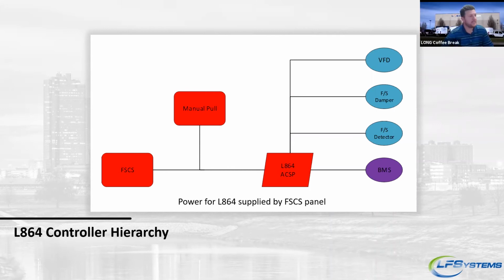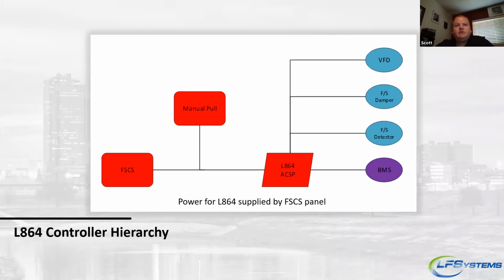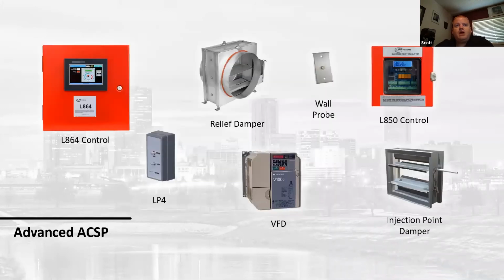So I understand this system works great for buildings 10 stories and below, but what do we do when we start getting into larger buildings? Great question. When you get into larger buildings, we recommend our advanced ACSP. As you see here, it's got an L864 controller, your pressure transducers, relief damper, and VFDs, but it adds in an 850 controller and an injection point damper.